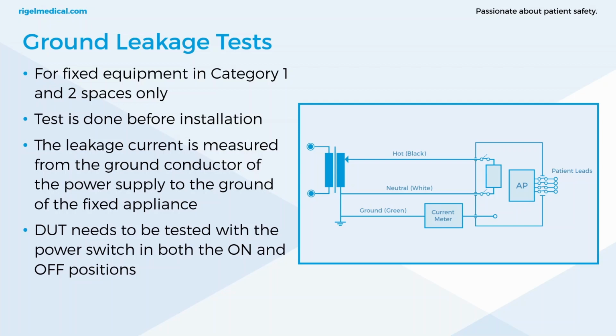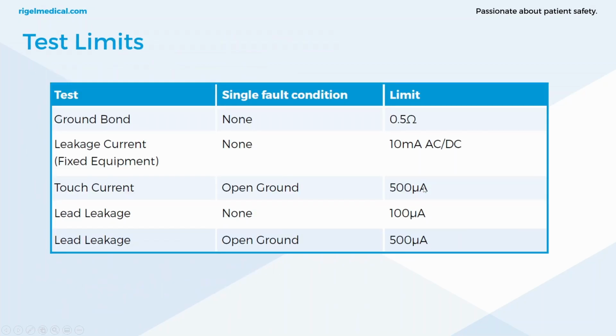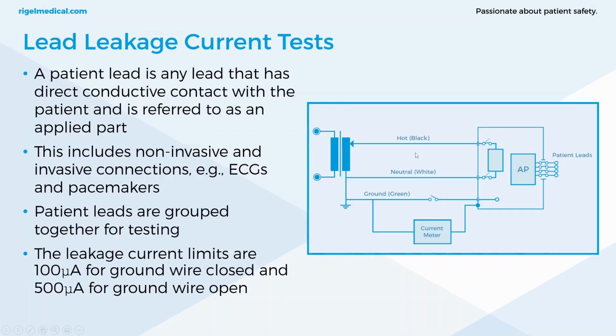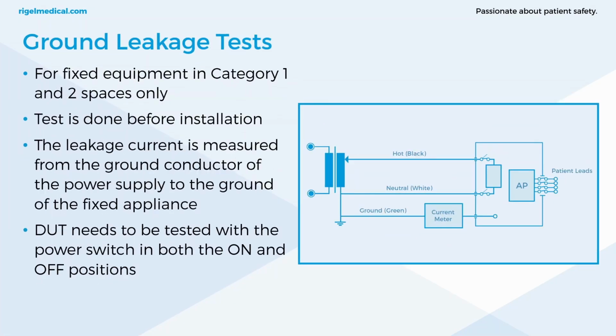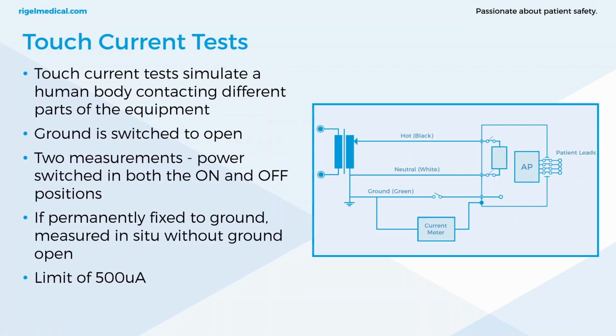So leakage current is measured from the ground conductor of the power supply to the ground of the fixed appliance. And the current limit for this, although it's not on here, is 10 milliamps AC and DC. You're performing this test in both the on and off positions for the power switch of the device, and it's the same limit, 10 milliamps. It's a relatively straightforward test, and it's not going to be performed on many devices.